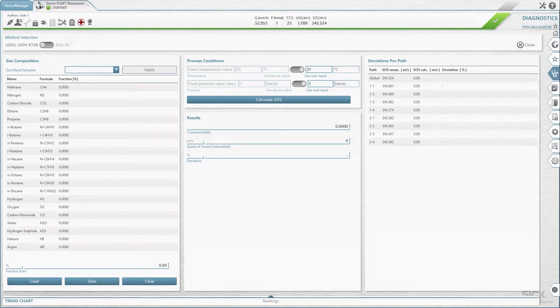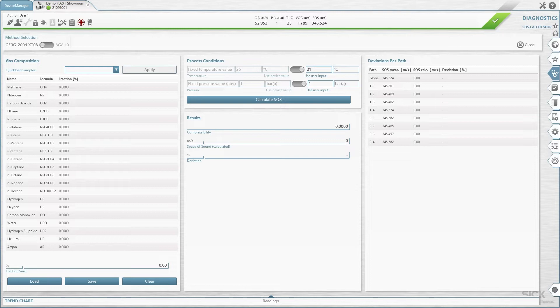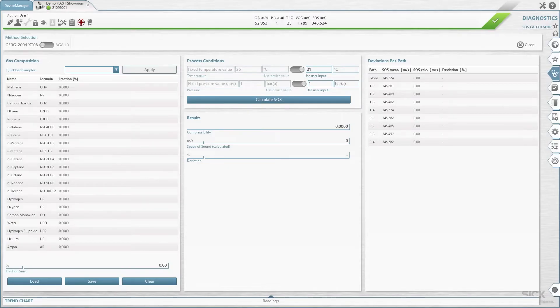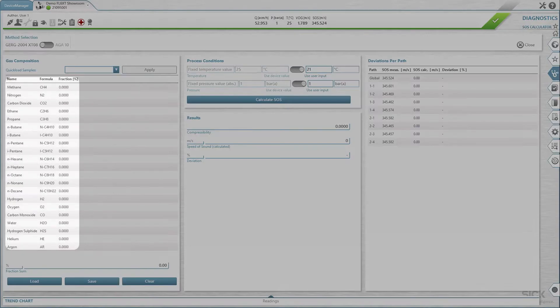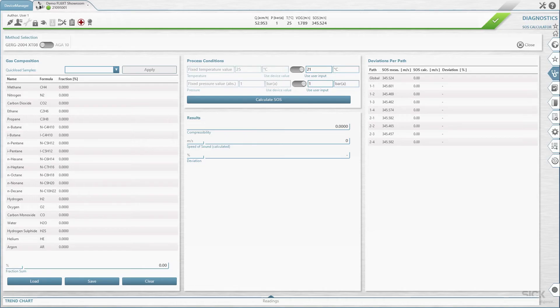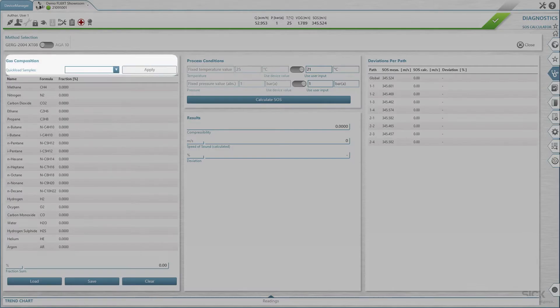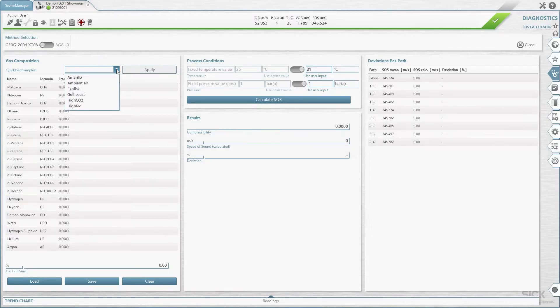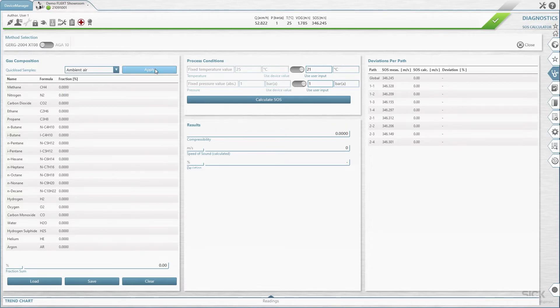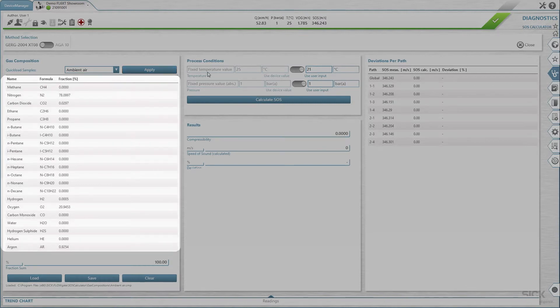To calculate the speed of sound, it is necessary to define the composition of the application gas. A set of standard gas compositions is available for quick access. To load a standard gas composition, first go to the panel Gas Composition and select a composition in the drop-down box Quick Load Samples. Click on Apply. The list of components will be filled with the selected gas composition.